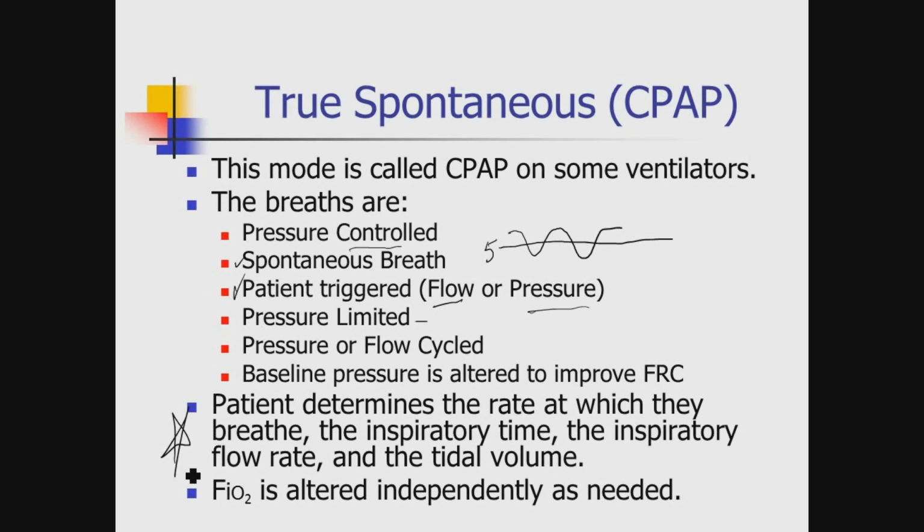It's basically just allowing them to access a gas source. And we set the FiO2 and whatever they want to breathe, they breathe. The beauty of it is I have alarms and I have apnea parameters. So if they stop, I got some backup. Put them on a T-piece and they stop breathing. Oh well. Nice knowing you. Not much you can do there. Concept makes sense.